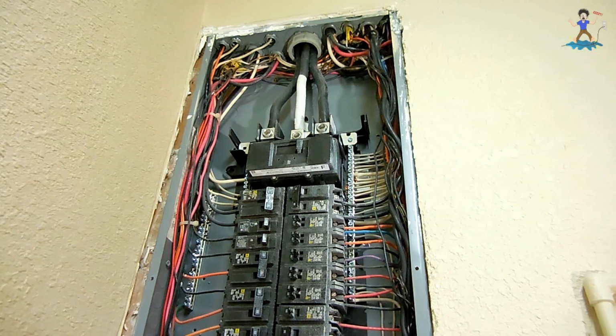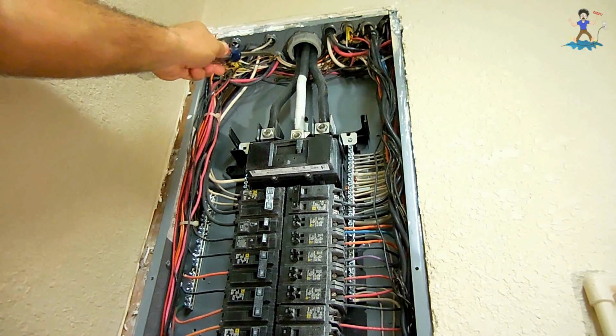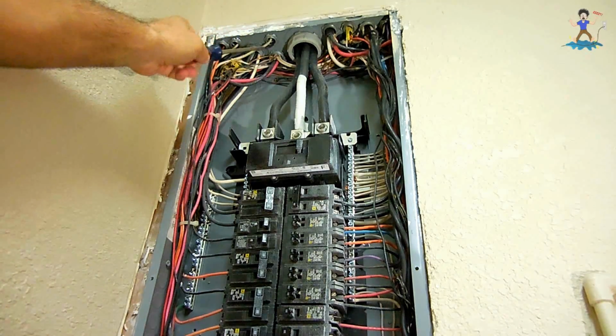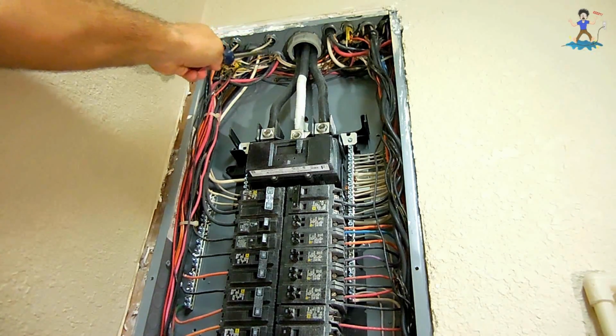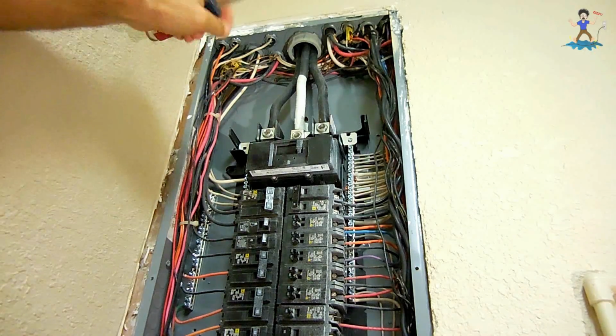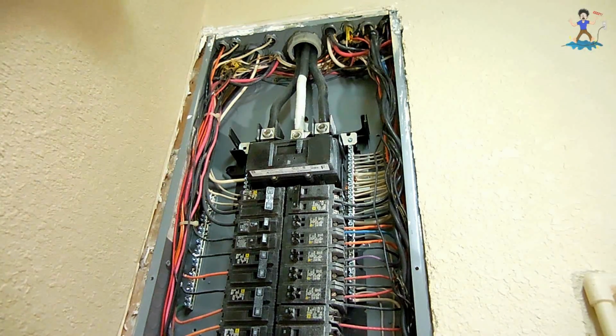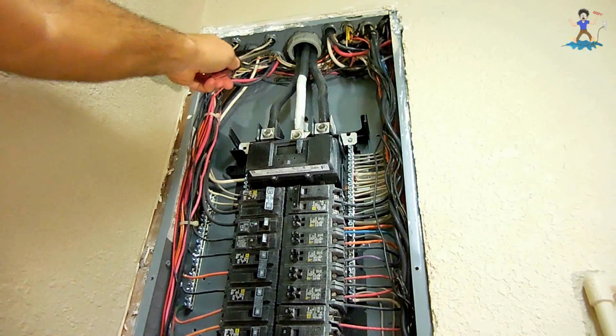If you notice that one of the wires gives a lower reading than the other 2 or 3, then you're going to know that that's the wire which has the problem with the insulation, and you're going to have to replace that wire or inspect further from the panel to see what the problem may be. It's also an excellent idea to use a Megger when pulling a new wire through conduit into a breaker panel. So if you look at the top of the panel right here, you can see this metal conduit with the white wire and the black.